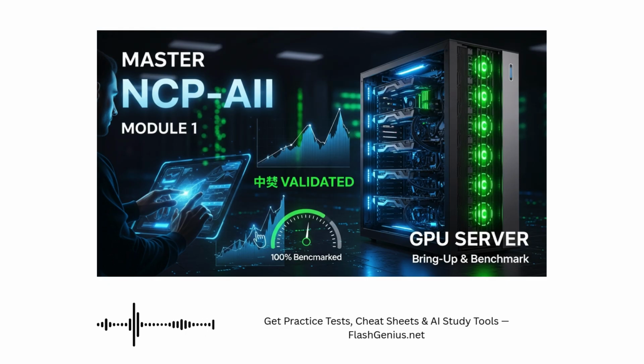That leads us to the final two steps, the validation phase. Step 6 is initial light validation, think of it as a quick health check. You run nvidia-smi to make sure all the GPUs are detected, ping other nodes and the gateway to check network connectivity, and look at sensor data to make sure baseline temps and voltages look normal.